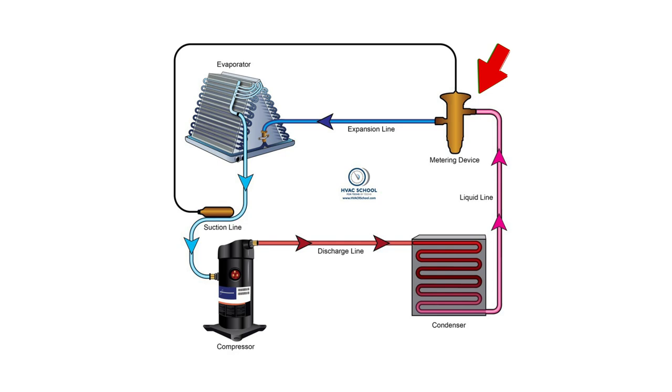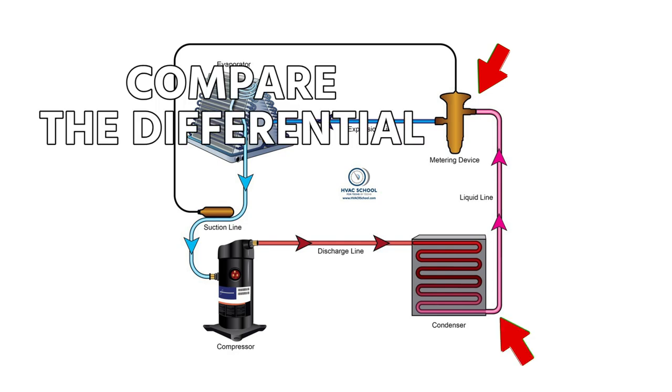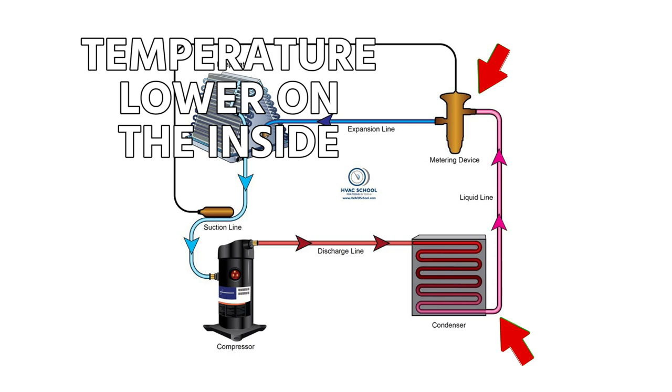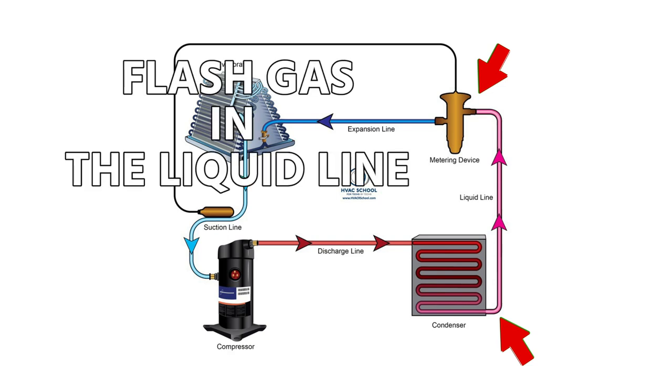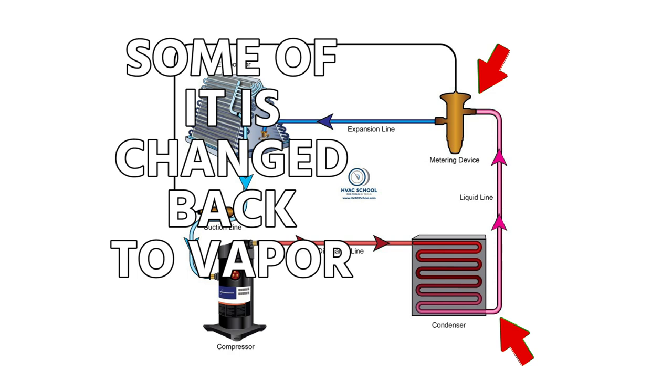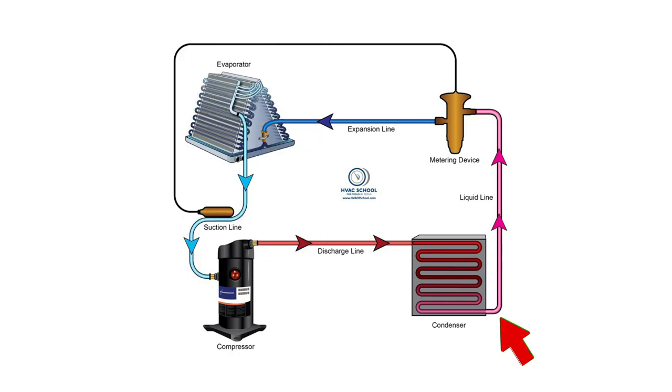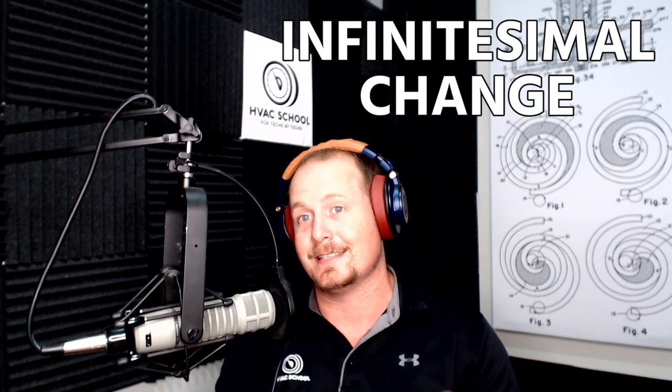Measuring your liquid line temperature in the right location is important. There is an argument to be made to measure your liquid line temperature both inside and outside and compare the differential, because you really shouldn't see any significant difference. If there is a difference where the temperature is lower on the inside than on the outside — meaning lower near the metering device than near the condenser — that's an indication of flash gas in the liquid line, meaning some of it is changing back to vapor. That's lost efficiency. We want to make sure our liquid line, as it leaves the condenser and enters your metering device near the evaporator, is pretty much the same temperature. A measurable temperature change occurs if there's enough pressure drop that all of the subcooling is taken up and it's actually beginning to boil again — that's the concept of flash gas.